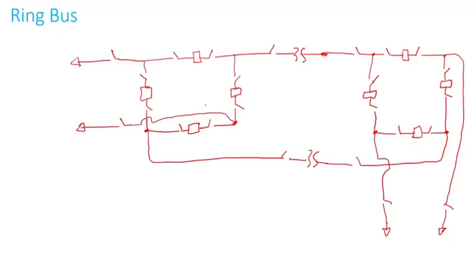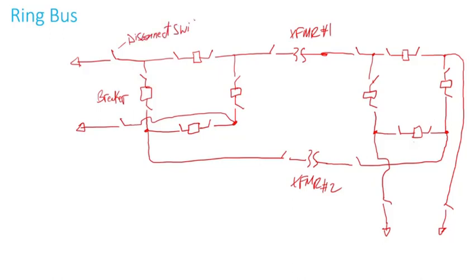Here's another example. Instead of a straight bus, we have transformer one and transformer two in a ring bus topology. A circuit breaker is capable of interrupting fault current. A disconnect switch, on the other hand, is typically not capable of breaking or interrupting fault current. Disconnect switches can break load only if they have an interrupting device, and you also have to worry about charging current.